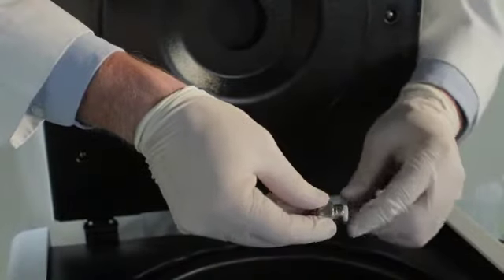The Hematology Pro Stainer has only 2 nozzles. The A, B, and C reagents spray out of the same front nozzle. The D reagents spray from the back nozzle. The ABC nozzle does not have an O-ring, and it also has a mixing insert.